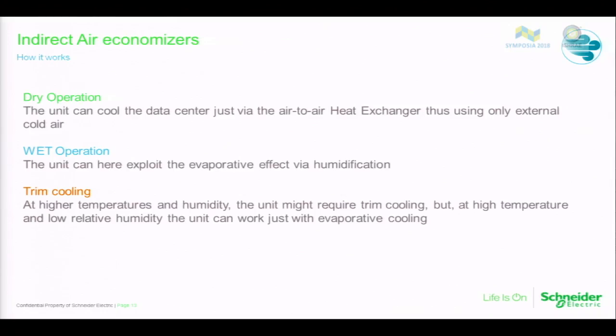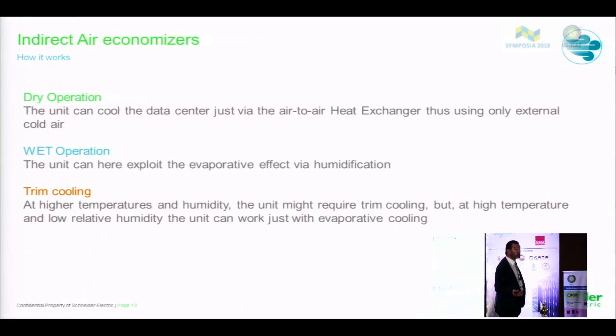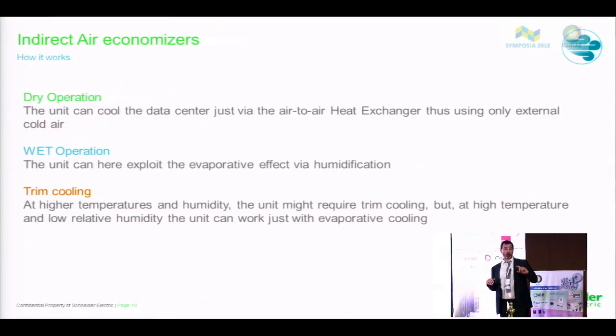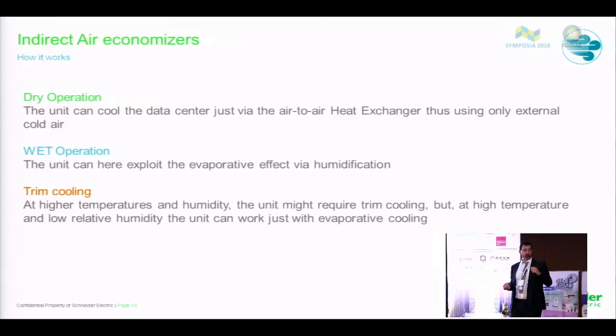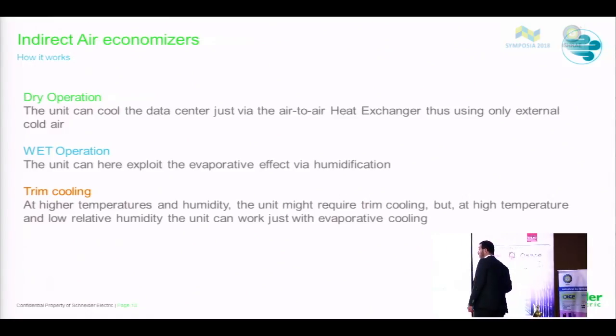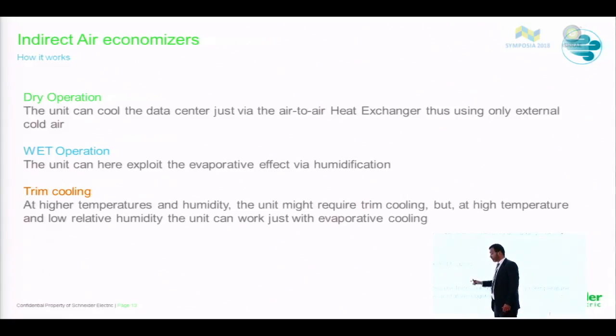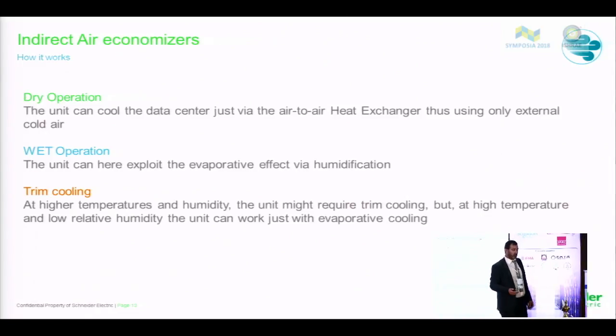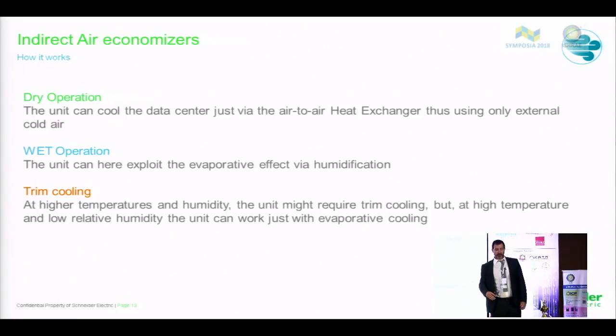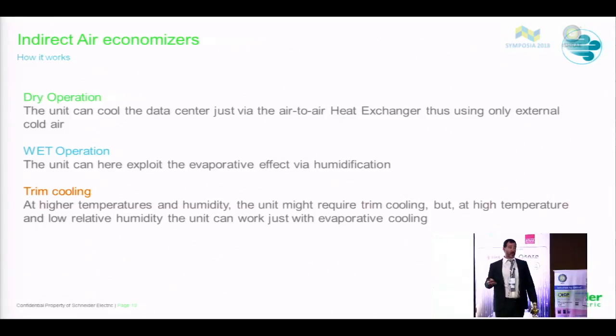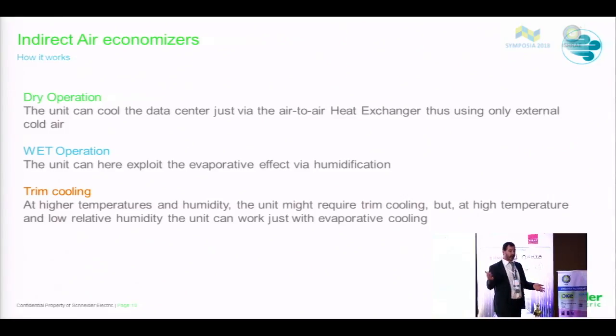So, in winter time, there is just air that enters into the heat exchanger, and that's all. When it is not enough, the heat exchanger is wet, with this adiabatic system. When this is not enough again, because it's too warm, even the compressor covers the capacity, which is the portion which is not covered by the heat exchanger. So these three areas are managed by the control board, and the water consumption really depends on the climatic profile. So it is not possible to say if a solution like this is applicable or not applicable. It depends on the climatic profile, on the humidity level of each region.